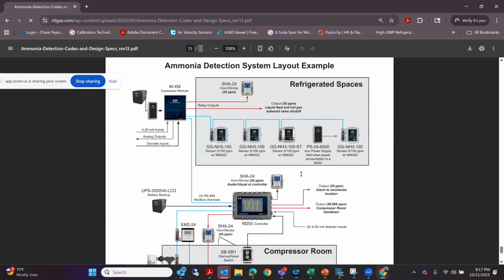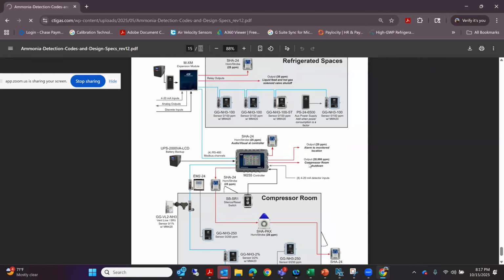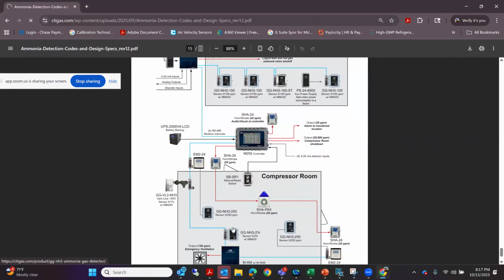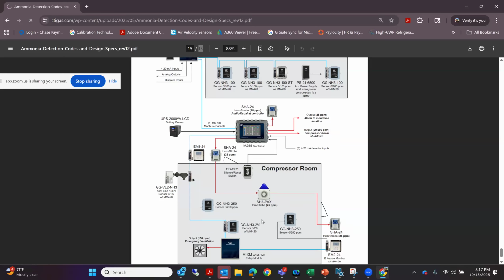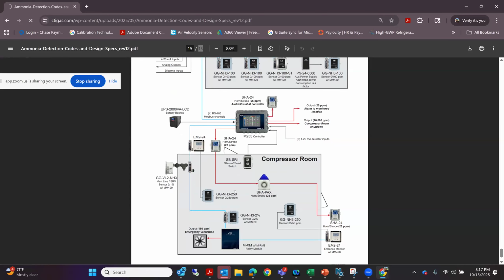And so when you're designing your systems, one of the things to always be aware of is, hey, it's one thing, let's get all of our sensor points figured out. And as I showed before, CTI does recommend this high-level sensor in their design, because once you go to 250, and then somebody's responding to a leak, the fire department is usually going to ask, have you made it over 10,000 parts per million yet? If the fire department is supposed to be responding to help you out on that release, they like to kind of know, because if all you can read off your controller is 250, then you really don't know if you've reached 10,000. So that's one of the questions they like to ask. My understanding is when the fire chiefs show up and the authority having jurisdiction, and they have to do a life-saving event, a lot of times they're going to ask, are you over 10,000 or not?